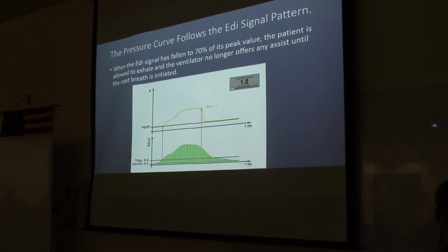So the pressure support curve will follow the EDI signal pattern until the EDI signal has fallen to 70% of its initial value or peak value. Then pressure support will stop and the patient can exhale. So see if you can find that on the graph. We're looking for a fall in the EDI signal so that we know the patient is done breathing in. All right, so we see the signal from the diaphragm increasing, increasing, increasing, kind of plateaus, and now it's starting to fall down. And at this point, the ventilator will stop helping with inspiration.